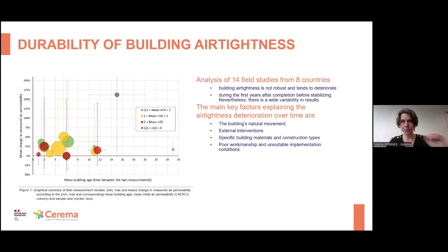The question of durability of building airtightness was also a very big one, and we have a big literature review published by the AIVC on this subject, because there is no point in making a requirement on airtightness if it just lasts a few months and 10 years later the airtightness is no longer good. What we've seen in most studies is that the permeability of the building increases by about 20% within a year after completion and then remains stable. So we have another research project right now to find out how we could make airtightness more durable, so the level measured at commissioning remains the same for a long time afterward.